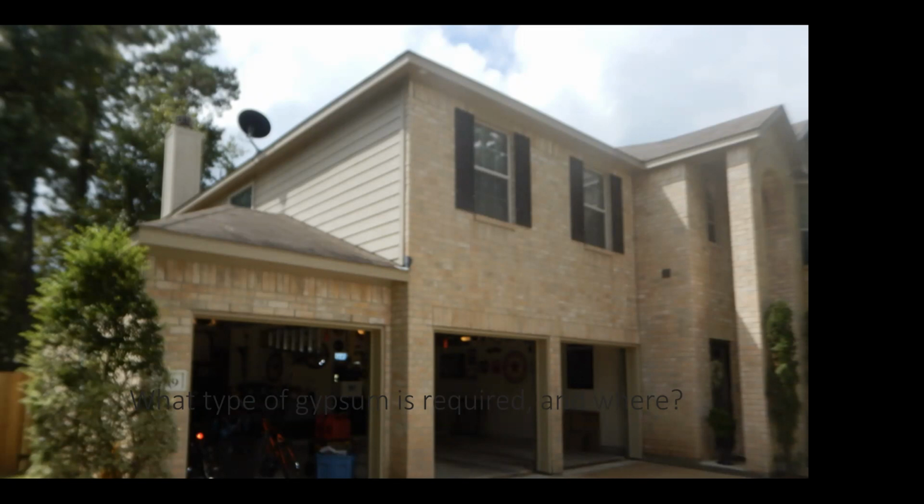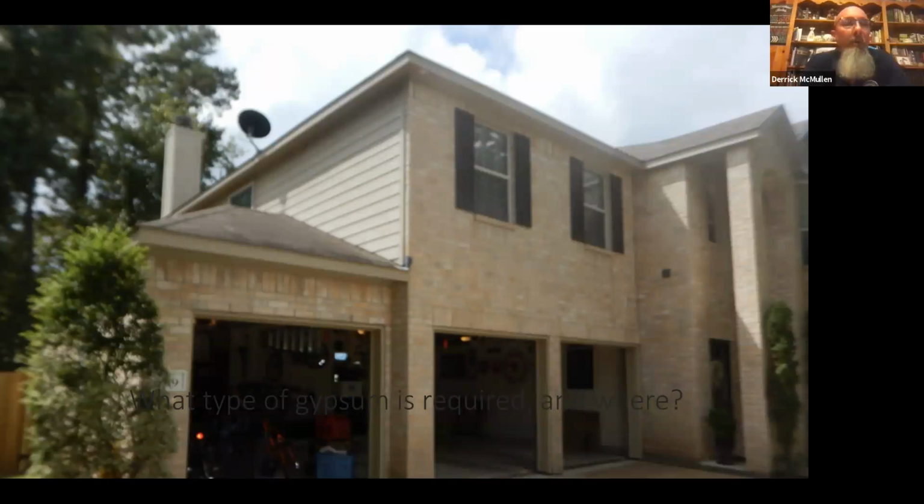This one says, I often see multiple holes, small gaps in the garage ceiling fixtures, light and door opener receptacle. They're small, but often several holes in the ceiling to attic between the two fixtures. I write them up, correct? Yes. Any openings between garage and attic you should note as a deficiency, unless it's a detached garage, obviously, but that's a different story. You'll see where people will want to hang bikes and they keep missing the ceiling joist and there's 9 holes there that are 1/4 inch wide. Technically, that's a violation. Simple to fix. You go get some caulk and you just squirt caulk in each hole. It's easy.